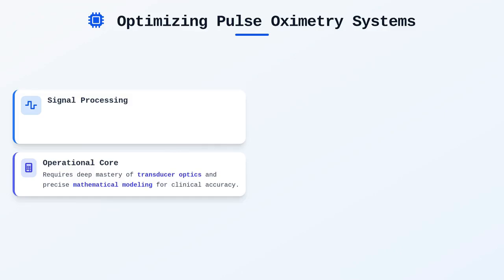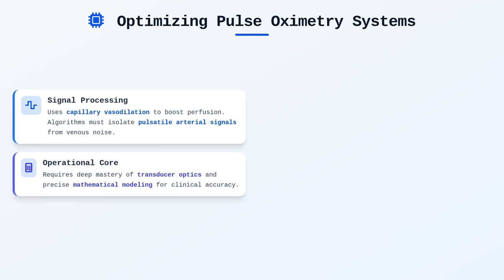Transcutaneous pulse oximetry, while related to co-oximetry, employs local capillary heat-induced vasodilation to improve perfusion at the sensor site. The accuracy of this measurement depends upon the ability of the algorithm to detect the pulsatile component of the arterial signal, effectively filtering out non-pulsatile venous and tissue background noise.